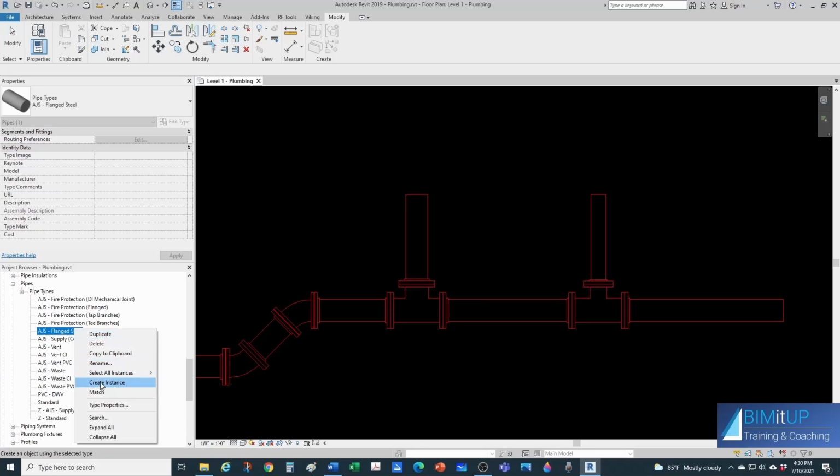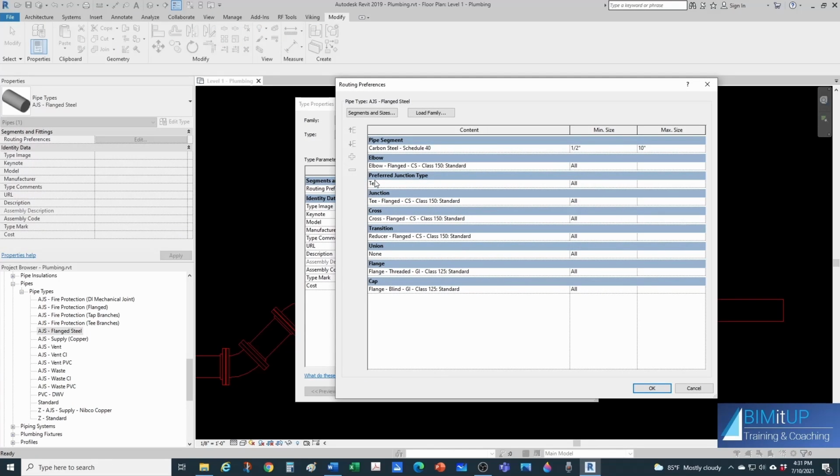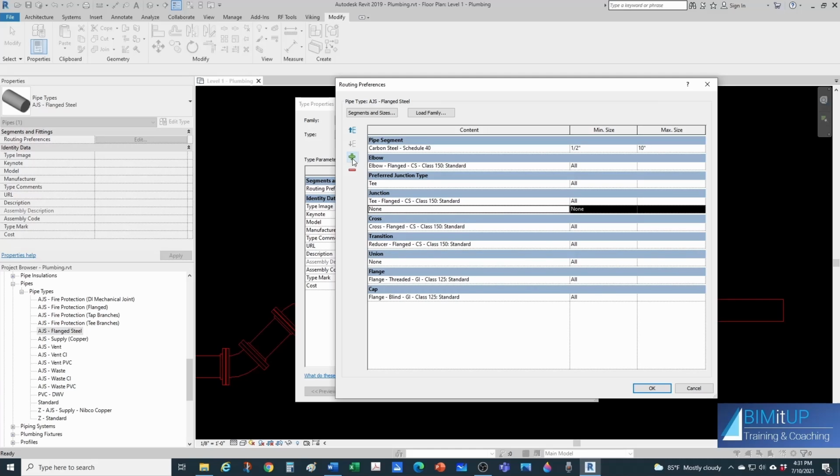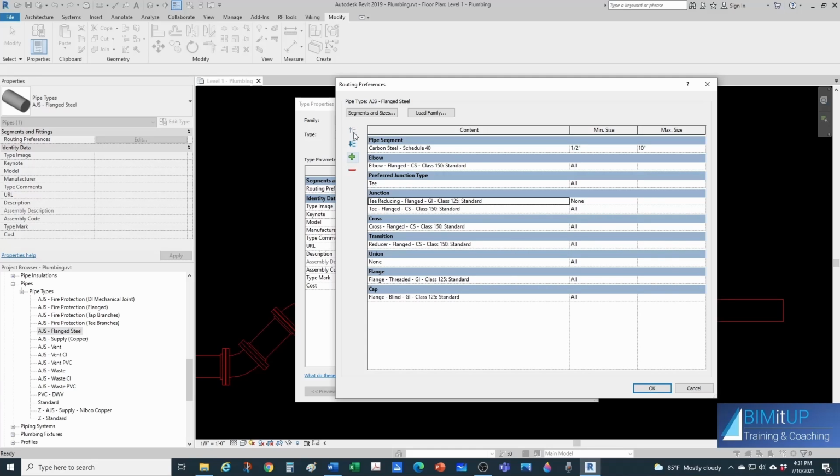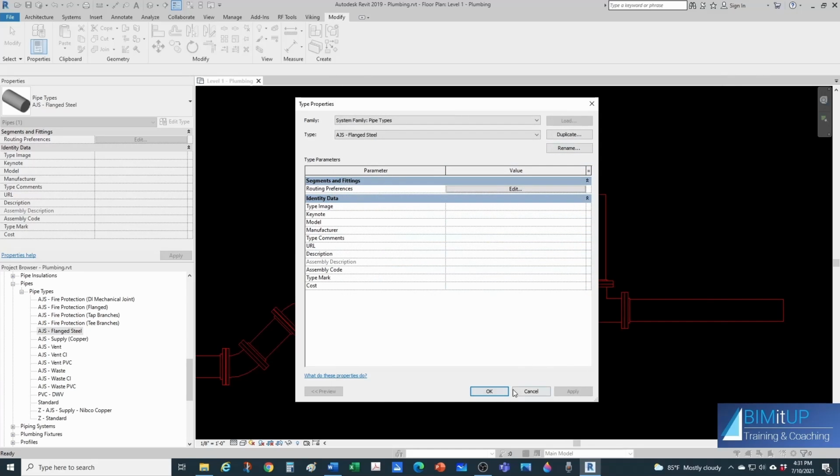So what you would have to do is come here, and then under junction, you would have to add, in addition to that standard flanged T, which would be like for 4x4x4 or 6x6x6 or 8x8x8, but not for a 6x6x4, for example. So you would have to come here and go into T reducing flange and take this to the top, and then you would use the reducing T for the sizes that were available. This reducing T would come all the way up to, let's say, a 10x10x8, but you couldn't do a 12x12. So what you would do is use this T for those large T's. But in this case, apparently we don't need them, so we should be good to go.